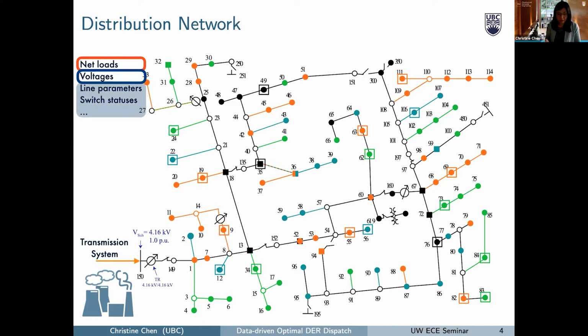In the case of global control, we would need some knowledge of the network over which power is delivered—the lines and line parameters, resistances, reactances, switch statuses. You can see in this network there are some switches, like this one and here, and in general all sorts of network-related parameters, load levels, transformer settings, and set points for devices in the system.